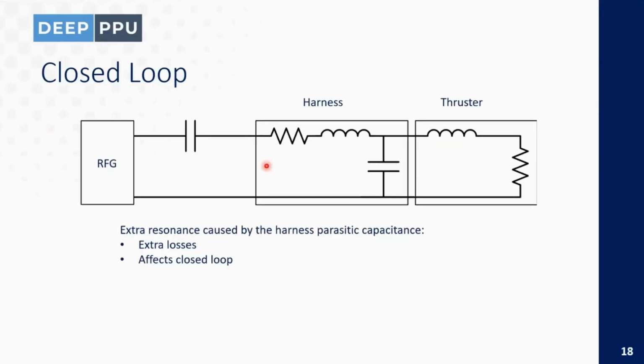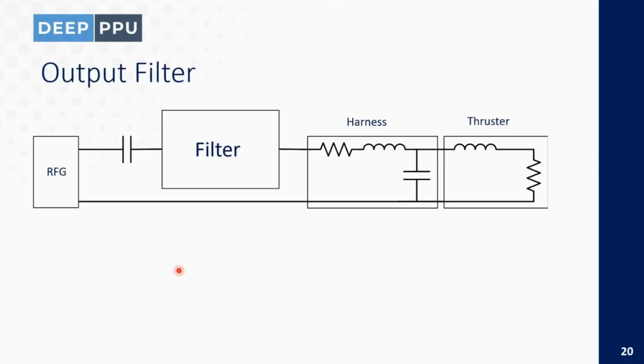So the effect of the harness is that we have extra current harmonics at high frequency. This creates extra losses and also affects the closed loop. So we need to filter the harmonics somehow - we need to add a filter. The first idea is to add a bandpass filter.